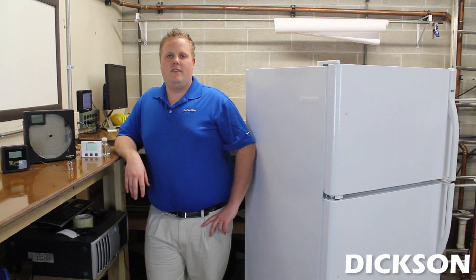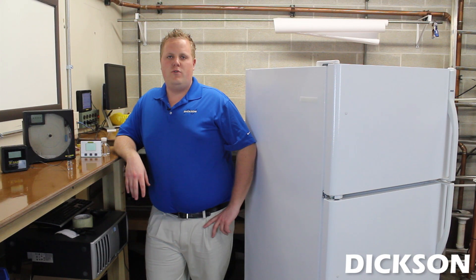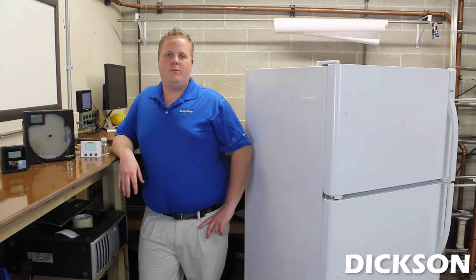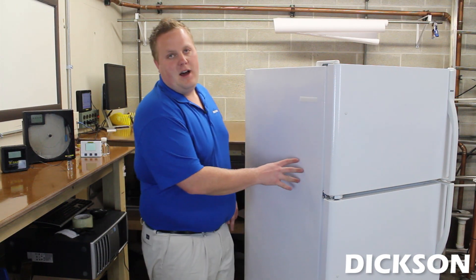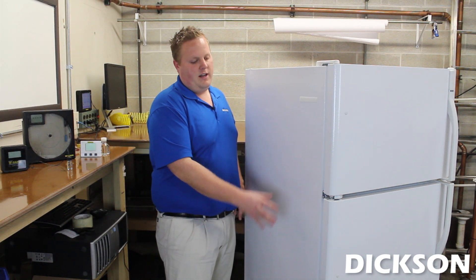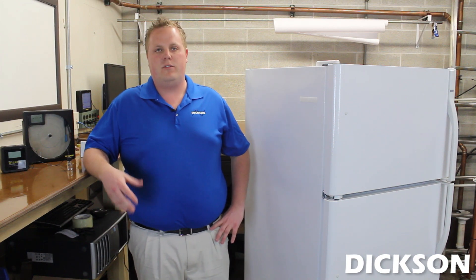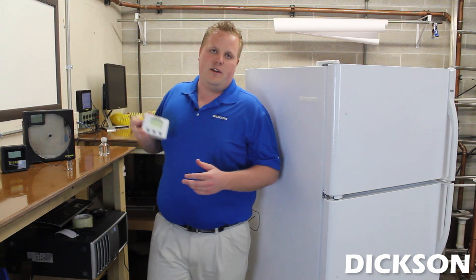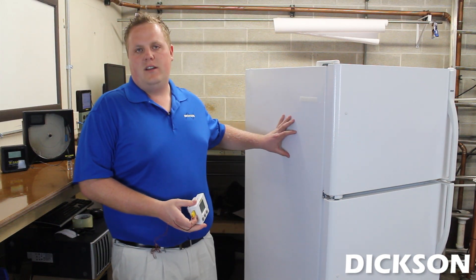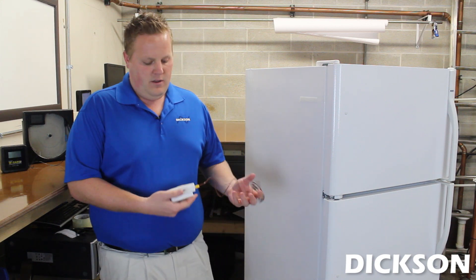Hi, my name is Jim Gibson. I'm with the Dickson Data Company. We're back here in our demonstration area today and I'm going to show you a few ways to run our K-type thermocouple probes into freezers and refrigerators. Our demonstration today will take place on a household freezer refrigerator, which a lot of labs use, but you can also use this technique on walk-in freezers and walk-in coolers as well. The reason you'd want to use a probe model is if the temperatures are way too cold for electronics, or if you're using our wireless product and you'd like that wireless signal to get out.